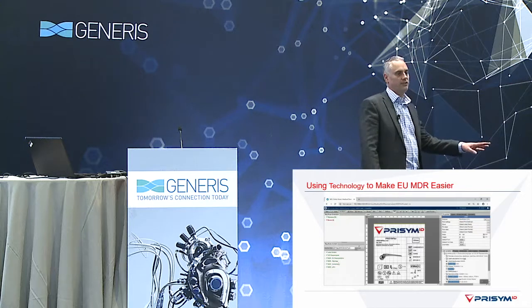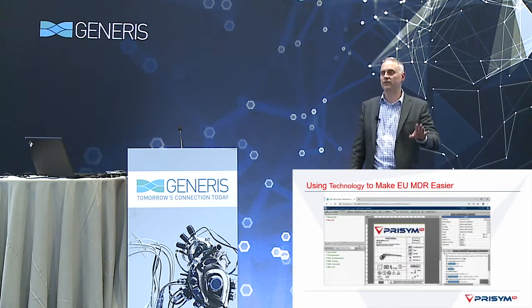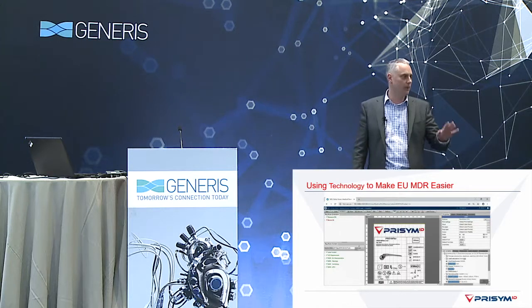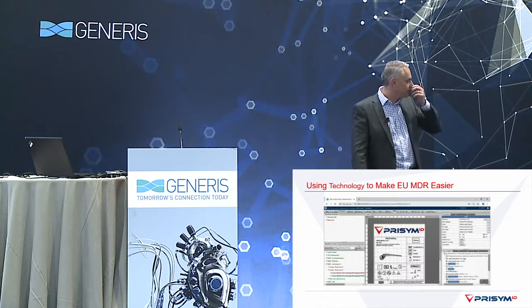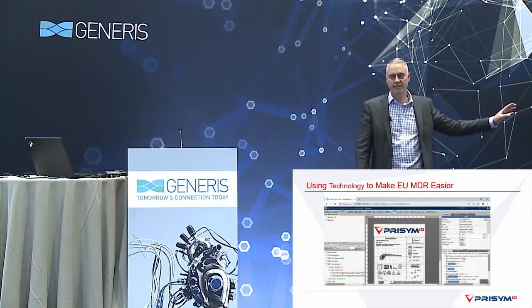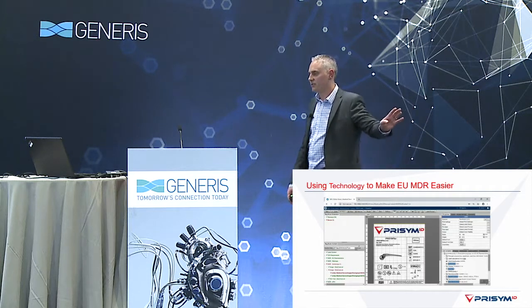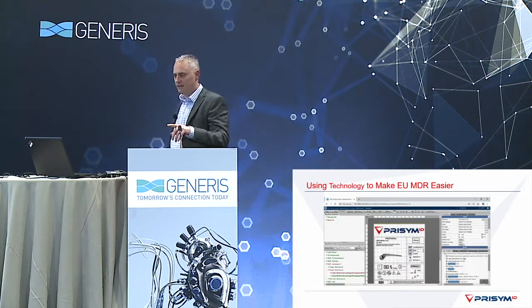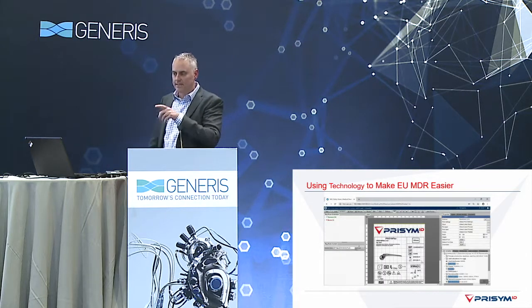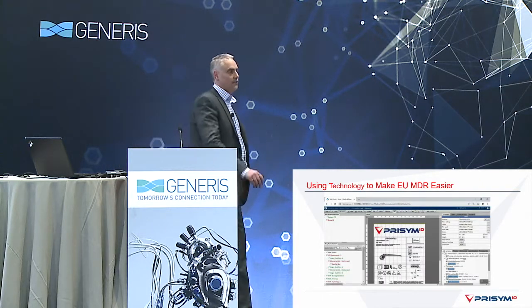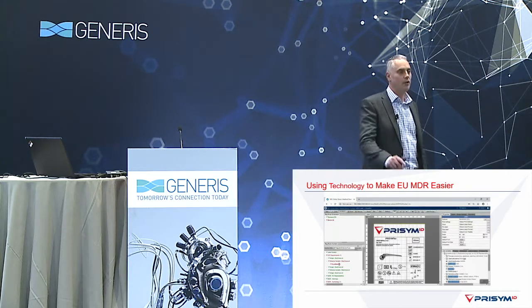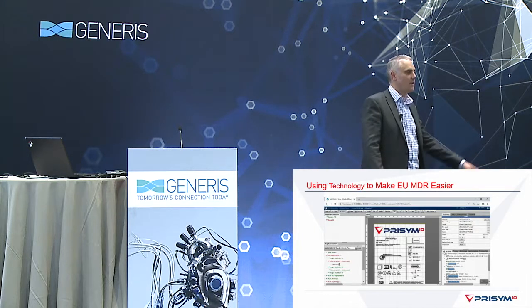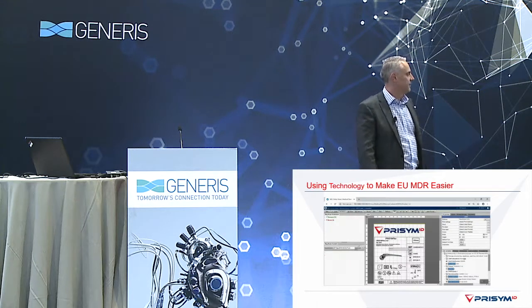So when your label designers are designing the labels, they are hand-held through making sure their labels are compliant to how you've interpreted the regulations. And you can see here that if the right symbol isn't in the right place or certain data isn't in the right place, so here we've deleted a latex symbol and someone is deleting the lot number, then on the left-hand side the software flags it up and says, whoa, you're missing things. You're missing a lot number that we know needs to be on this label, even if it's direct marking or an eIFU, for example. And we're also missing the latex symbol.